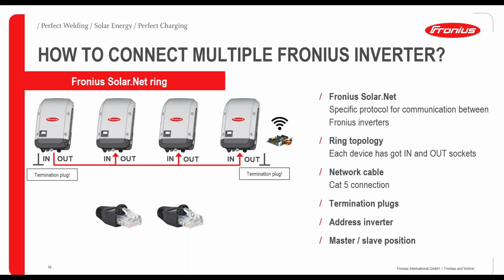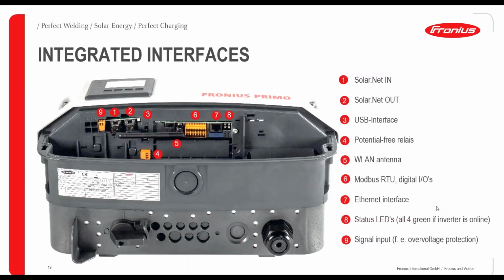And of course, to address the inverters, for example for four inverters, you have to set numbers 1, 2, 3, and 4. In case you have multiple data managers, that would also be possible, but you must be sure to set the master-slave position so one data manager is the master. In the normal case, you just have one data manager for the whole ring. That's important for connecting multiple Fronius inverters.